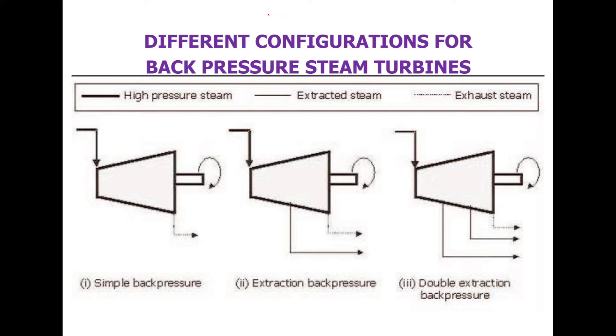The configurations involve high pressure steam, extracted steam, and exhaust steam. A simple backpressure is one type of configuration for backpressure steam turbines. Another is the extraction backpressure, and the third is the double extraction backpressure. In the simple backpressure type, there is a single entry and exit of steam through the turbine. In the extraction backpressure type, one additional exit is provided beyond the normal exit. The double extraction backpressure provides two extraction points between the entrance and exit of the turbine.